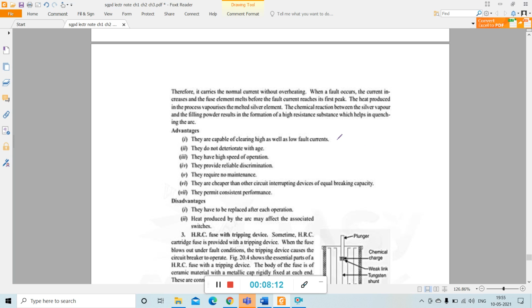So what are the advantages? It is capable of clearing high as well as low fault current, does not deteriorate with age, and has a high speed of operation. It provides reliable discrimination, requires no maintenance, is cheaper than other circuit interrupting devices of equal breaking capacity, and permits consistent performance.